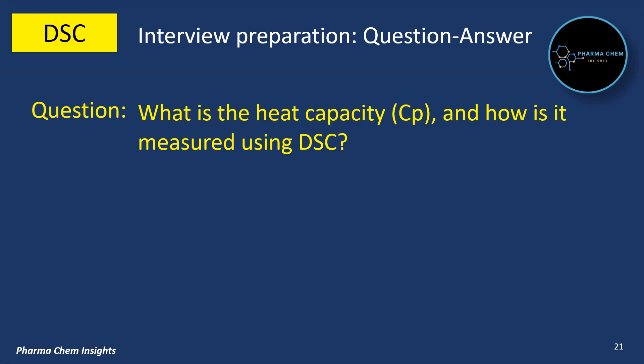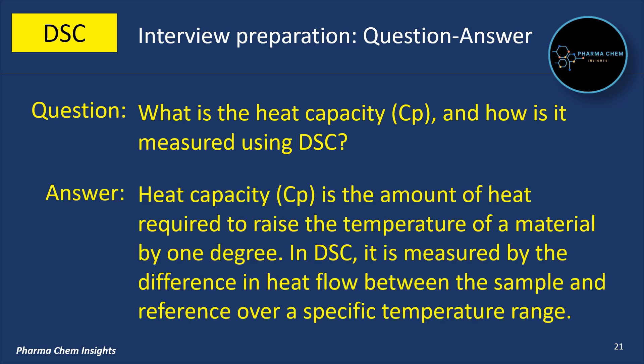Next question: What is heat capacity and how is it measured using DSC? Heat capacity is the amount of heat required to raise the temperature of a material by 1 degree. In DSC, it is measured by the difference in heat flow between the sample and reference over a specific temperature range.